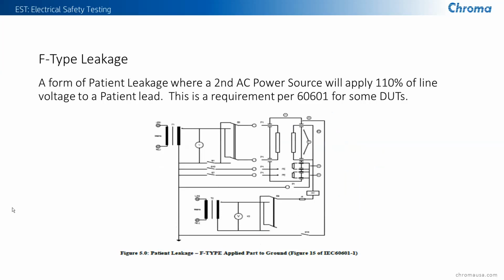There's another type of patient leakage, where there would be a second source of power that would be accessible to the patient. For instance, the patient might have a type of test equipment attached, and then the patient were to reach or be touched to another device, there wouldn't be a differential voltage or any way that there could be a shock hazard. This is defined in IEC 60601-1. We can also do testing to simulate that, and we'll go into that in more detail with our actual equipment.